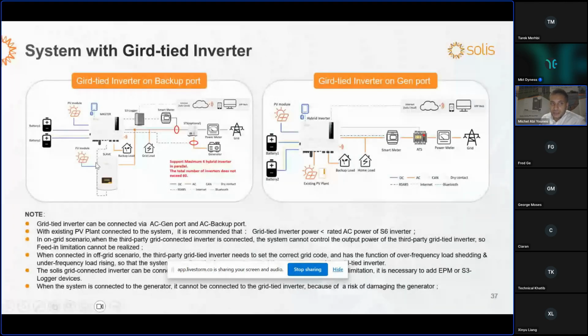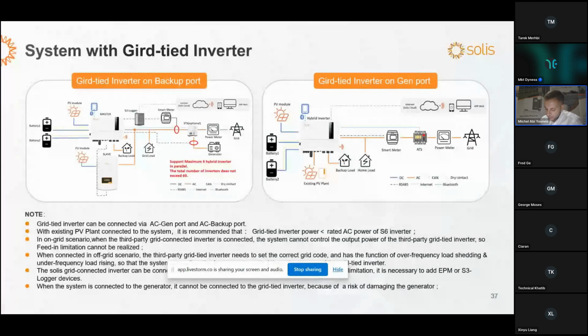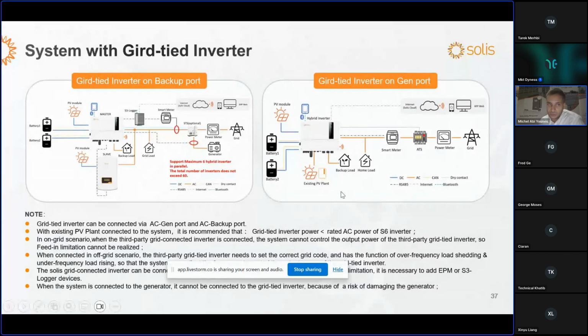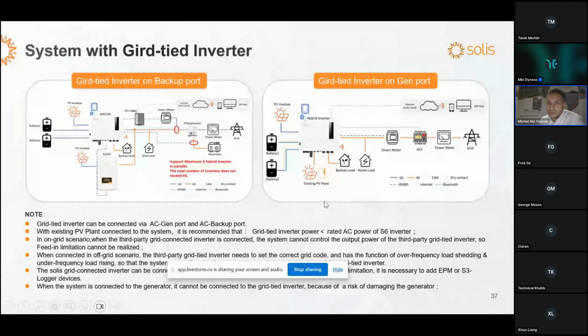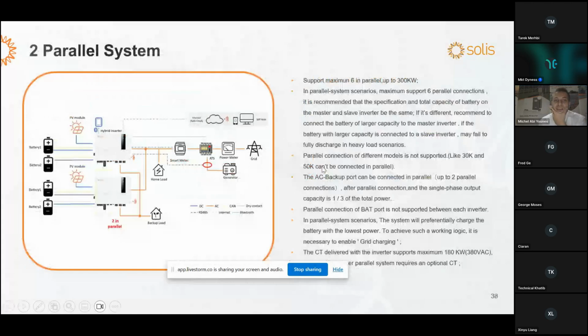Our inverter, as I said, can be AC coupled. If you already have an on-grid system installed and you want to upgrade it to hybrid, our hybrid inverter can be directly installed and can directly communicate with the on-grid inverter. The on-grid inverter can be connected either to the backup port or to the smart port, the gen port. Same goes if you are using multiple inverters in parallel. The generator, in this case, is recommended to be connected through an ATS on the grid port.